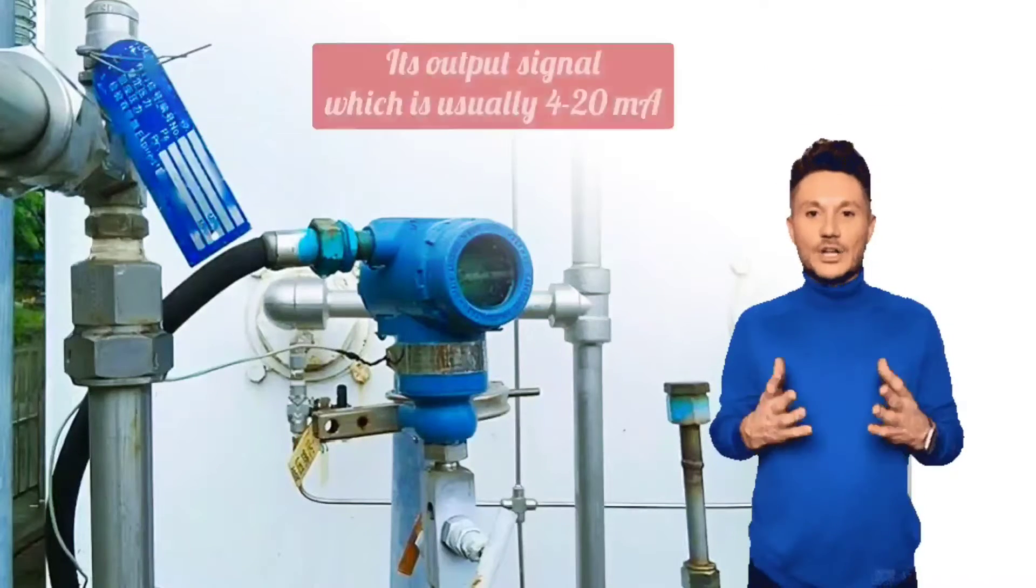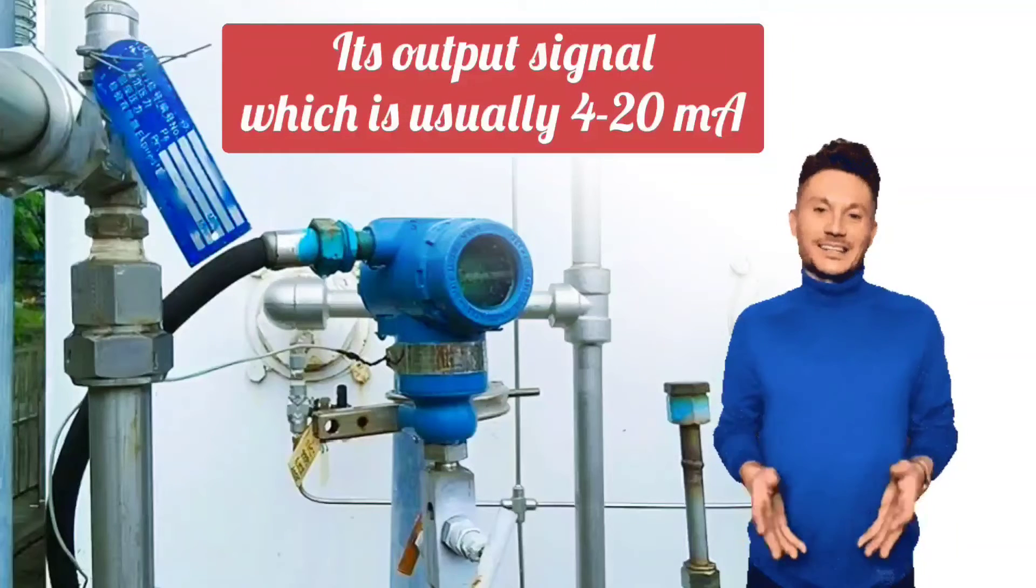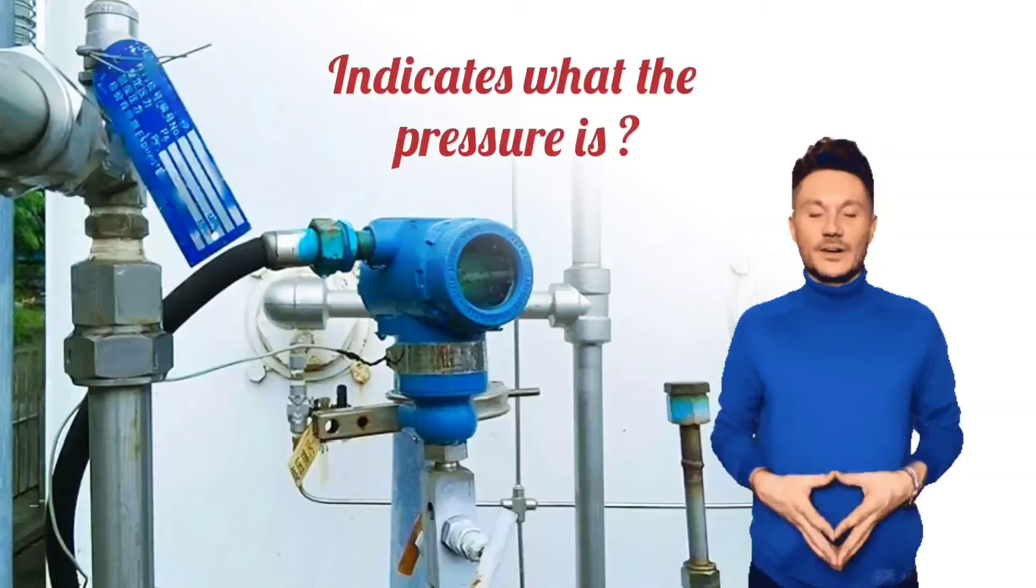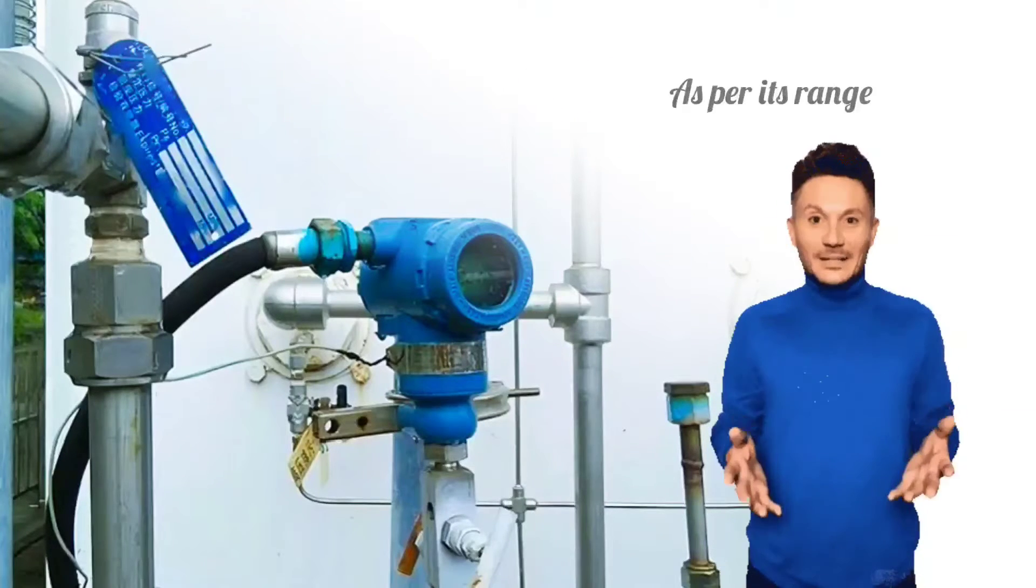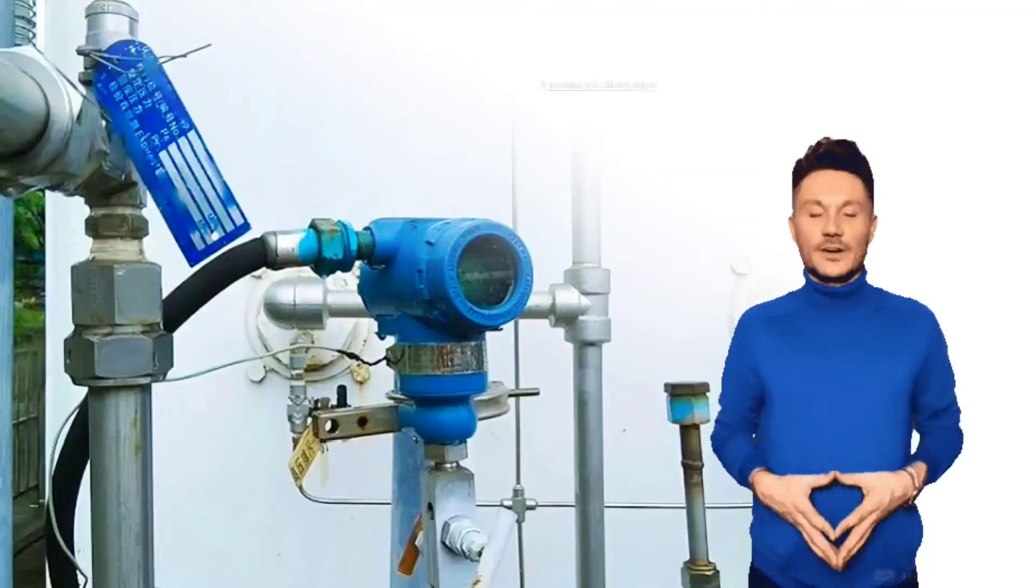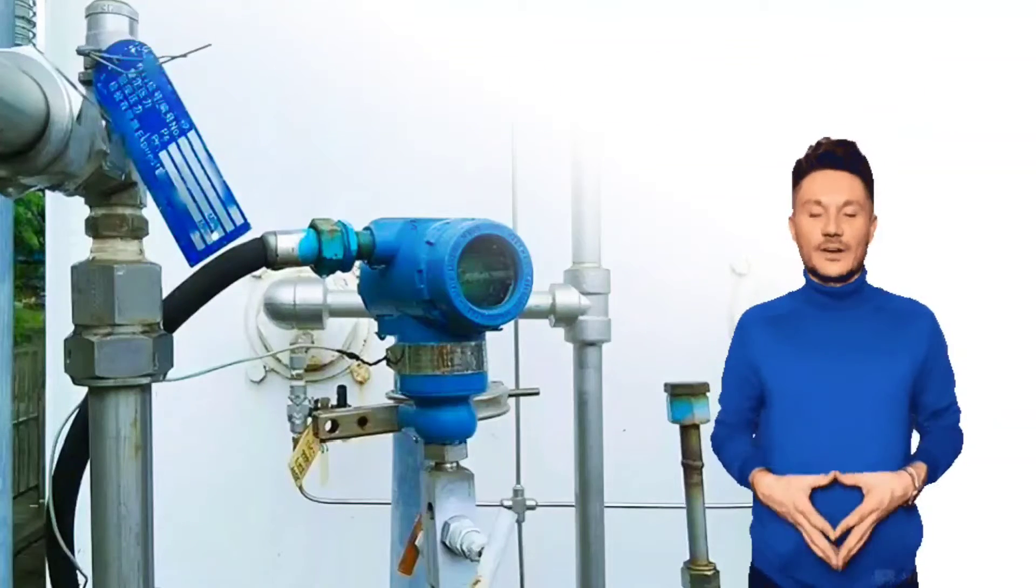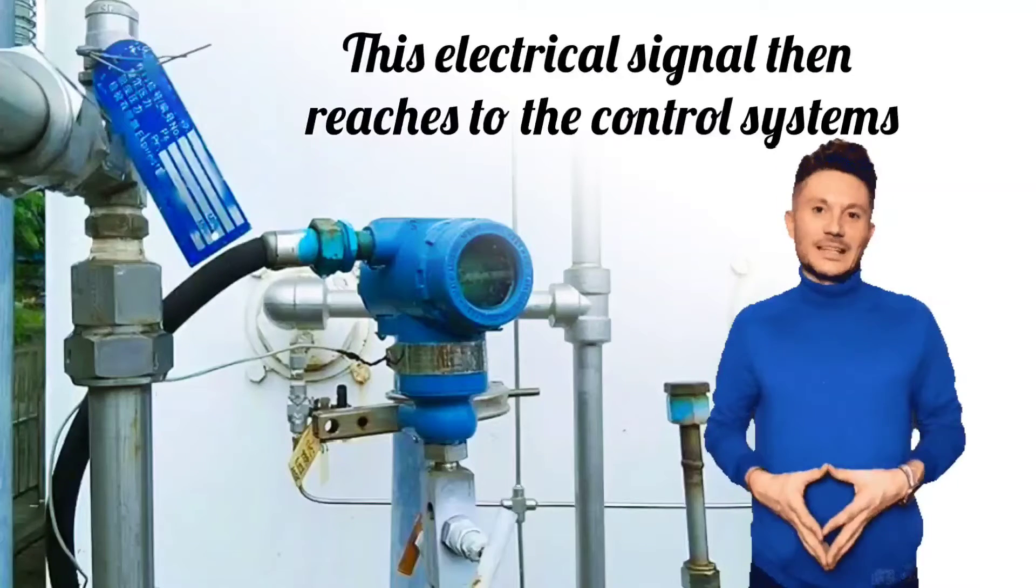Its output signal, which is usually 4 to 20 mA, indicates what the pressure is. As per its range, it provides 4 to 20 mA output signal. This electrical signal then reaches the control systems.